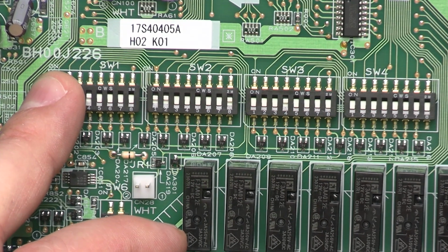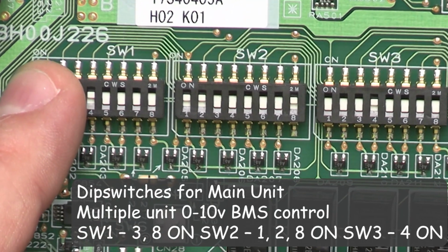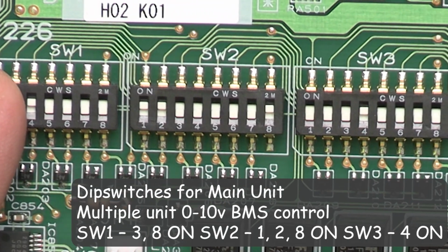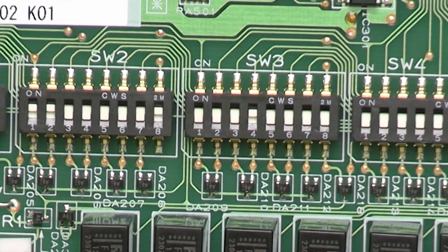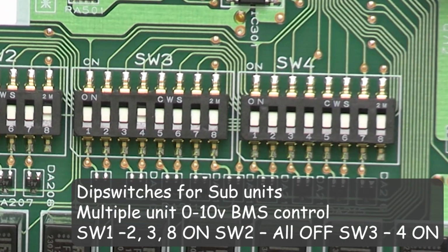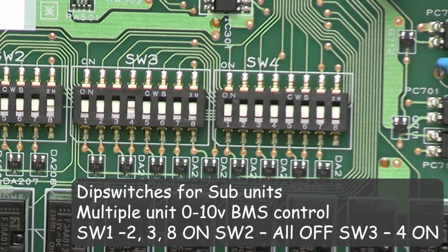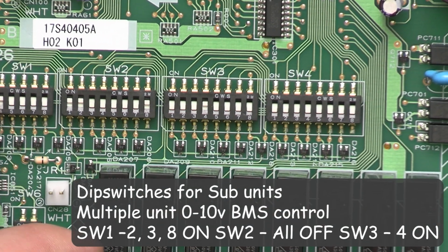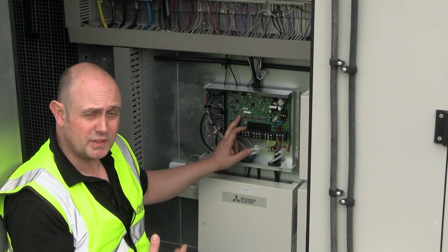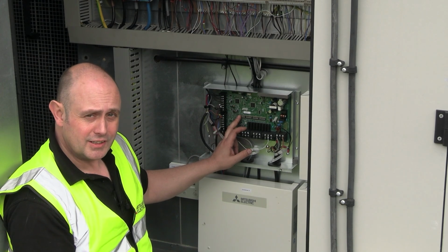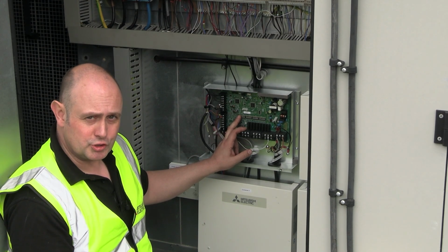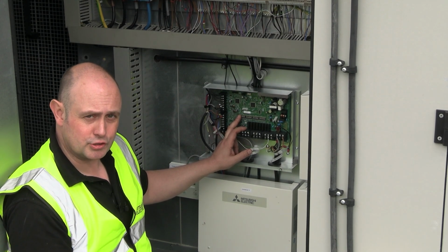The dip switches on this PAC-IF have been set up so that it can work with the air handling unit control we've got here. So in this situation we're going to control the temperature and the mode and things like that, and where it's on and off all via the air handling unit controller. So the dip switches here have all been set to reflect that. That means the dip switches might be different on your site, so you just need to have a look at those and make sure they've been set up correctly.